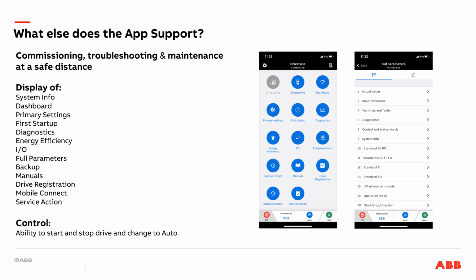Besides the ability to create backup and support packages, the Drivetune app supports commissioning, troubleshooting, and maintenance of the drive at a safe distance. After making the initial connection, you can move out of the arc flash area around the drive to work with primary settings to allow for fast configuration of the drive, or access the full parameters list. You can view diagnostic info and configure the I/O, and also generate service and support actions. It also allows you to start, stop, and put the drive into auto with the same functionality as the control panel itself.